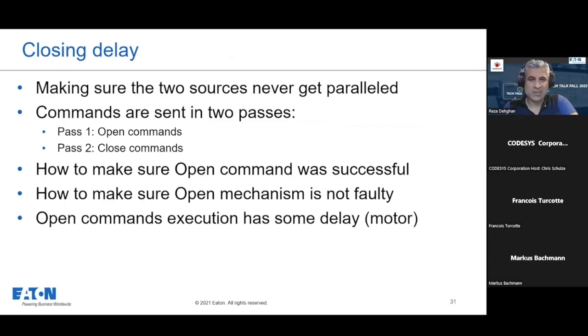Closing delay. That was another challenge, because making sure the two sources never get parallel is essential to the system. If for any reason we close all the breakers in the branch, that would be disastrous. So that's why we decided to send commands in two passes. We first send open on the breakers that need to be open. So we just make sure there is another check. There's always another check. Every time we send commands, we check that at least one breaker is open. That's internally. But to send the commands on the branch, we always do it in two passes.